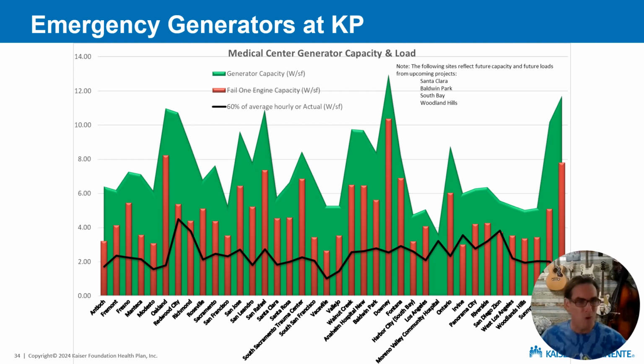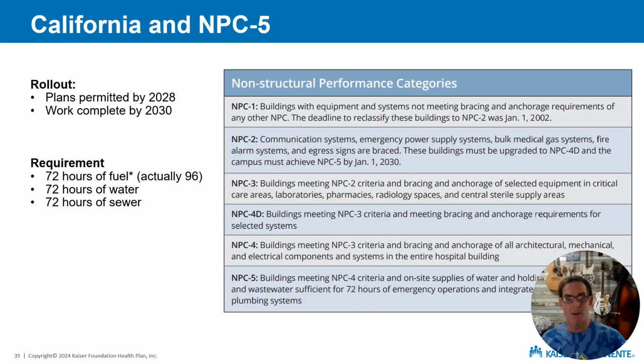The problem is so bad, by the way, that it can be difficult to test those generators on a monthly basis. In order to test a generator, you have to put at least 30% load on it. And so some hospitals have to buy load banks so that they can perform that testing because they can't get 30% load onto the generator with what's connected. So to double down on this, in the state of California, we have requirements called NPC 5. Those need to be in place by 2030. We need to have 96 hours of fuel, 72 hours of water and sewer storage on site for emergencies.